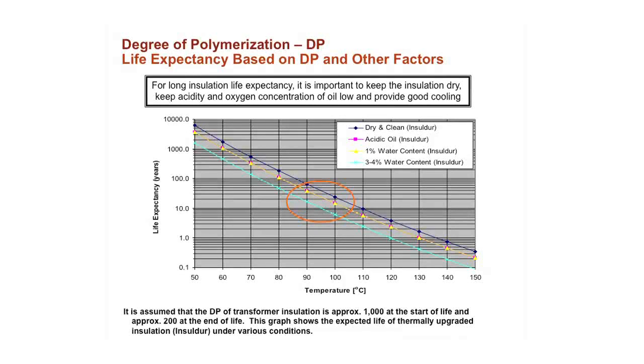I can also tell you how cellulose ages: if you had 105 degrees for your cellulose, it can last about 18 to 20 years at that temperature. So by having high moisture, meaning instead of having 0.5%, having 2 or 3%, that almost doubles that aging rate. And the same with having high oxygen, that can double or triple the aging rate.